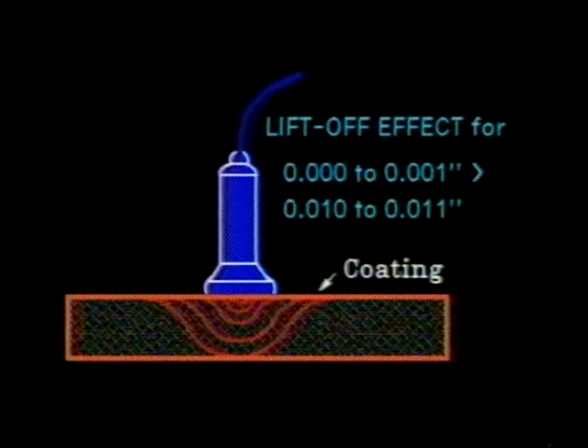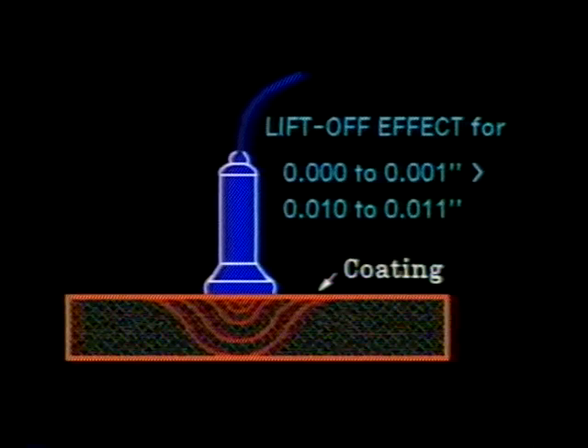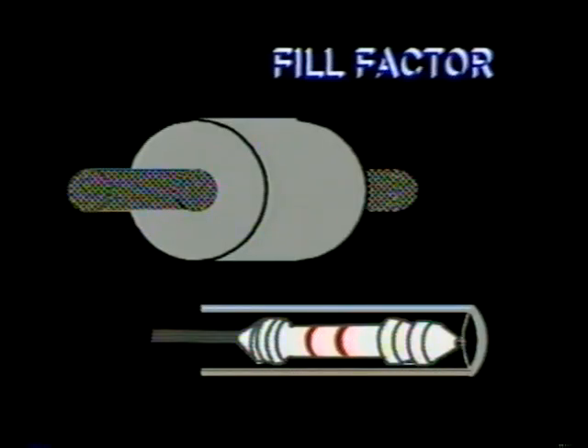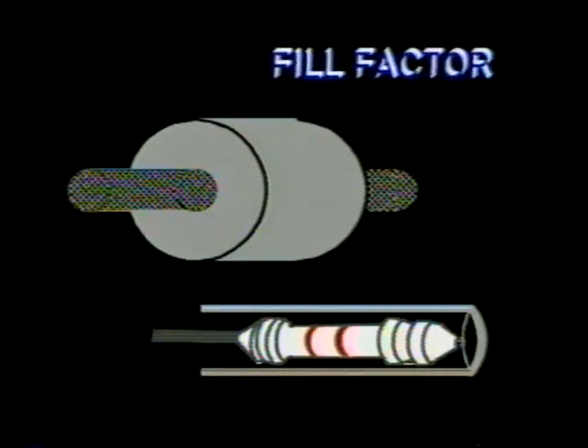Liftoff is also useful in profilometry and proximity applications. Liftoff is a term most applicable to testing objects with a surface or probe coil. Fill factor is a term used to describe how well a test object will be electromagnetically coupled to a test coil that surrounds or is inserted into the test object. It pertains only to inspections using bobbin or encircling coils. Like liftoff, electromagnetic coupling between test coil and test object is most efficient when the coil is nearest the surface of the part.